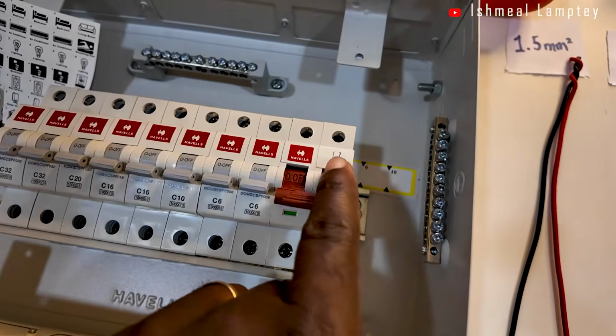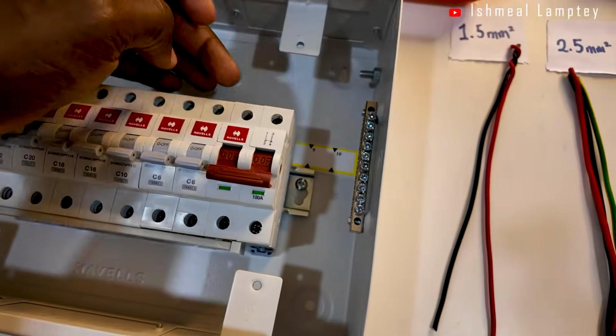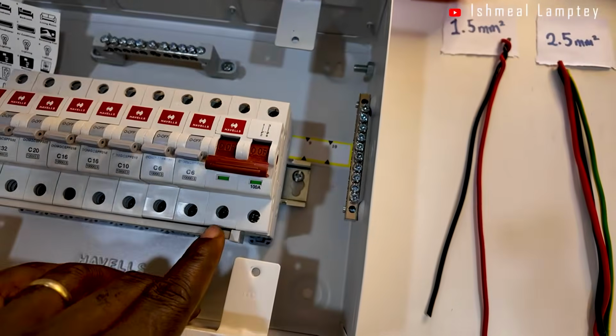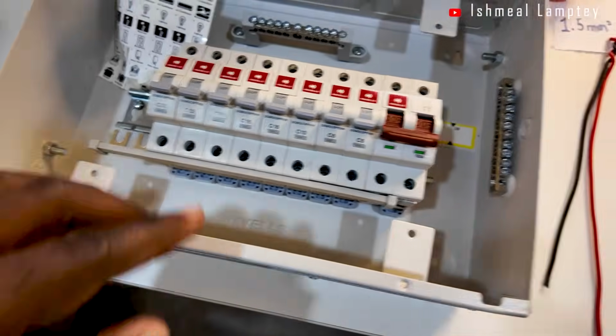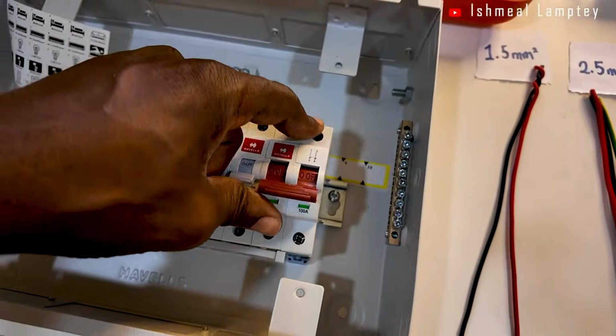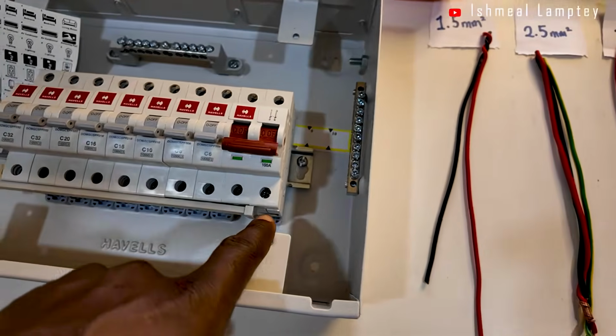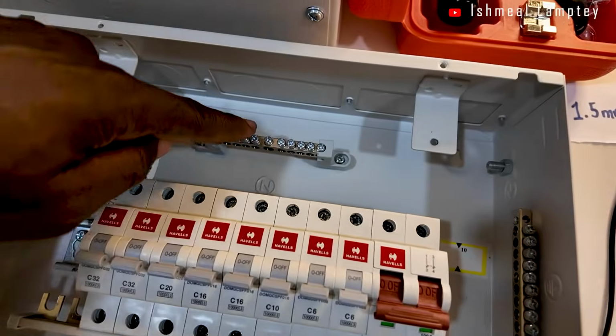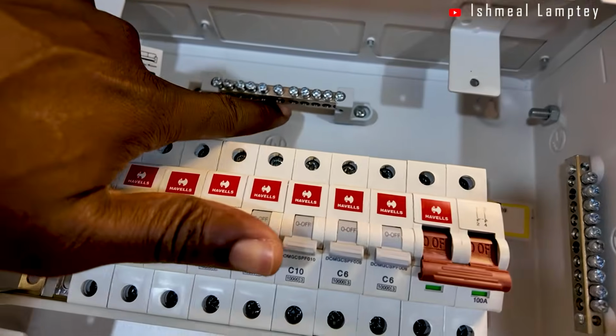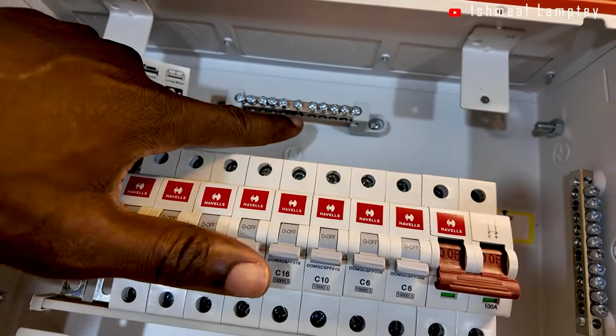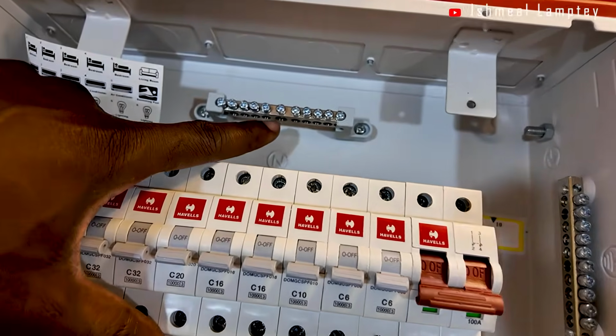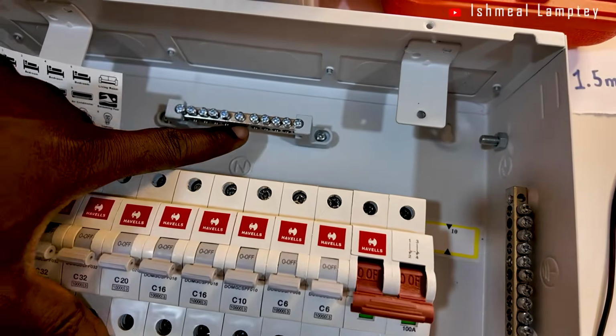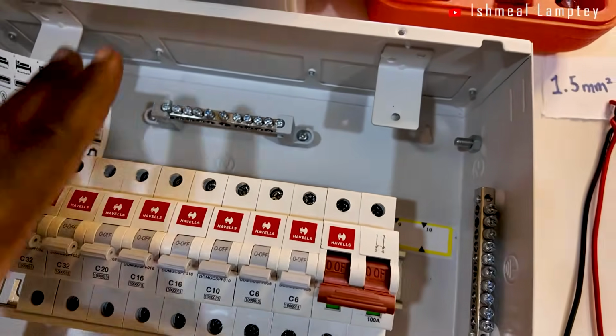If you look at this breaker, it says 1, 2, 3, 4. You have your power line coming into 1, coming out from 2, and being distributed to all these breakers. Then you have your neutral line coming into 3, taken out from 4, and distributed to the neutral bus bar, which has a big spot here for a bigger size cable, like 10 mm, 16 mm, or 6 mm, among others.